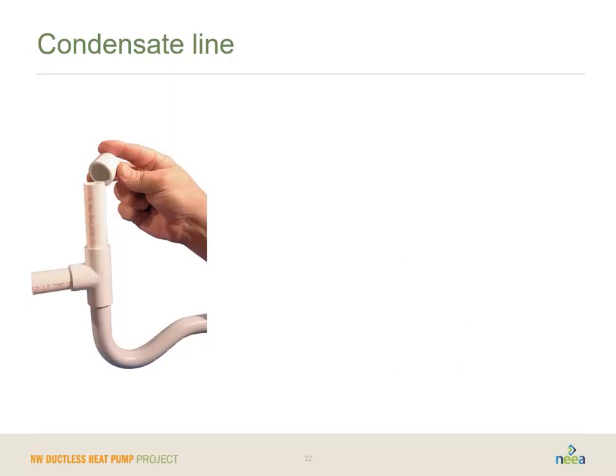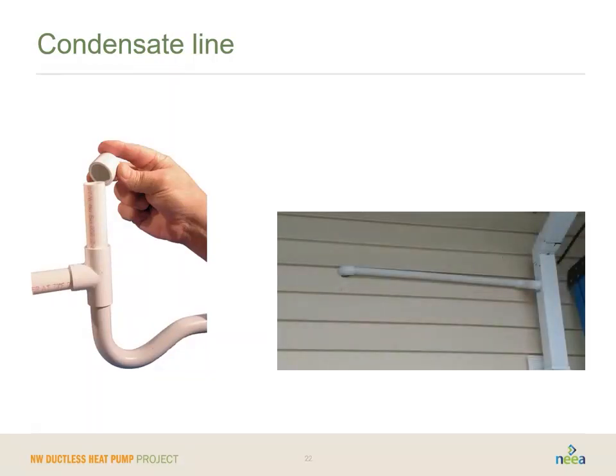The condensate line. As a part of the way these systems operate, condensation is created in the indoor head, and that condensation needs to go somewhere. So it's recommended that you bring that condensate line to the exterior of the building. One of the tricks you see on the right-hand side of the screen is this clever installer actually ran the condensate line directly to a downspout. So this has a way for that condensate to actually move itself away from the building and not create any wet spots either on the siding or at the base of the building.